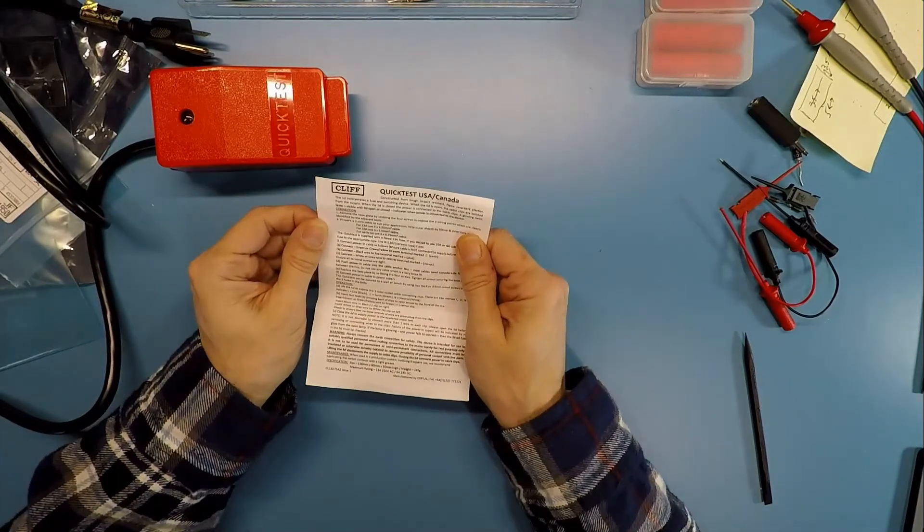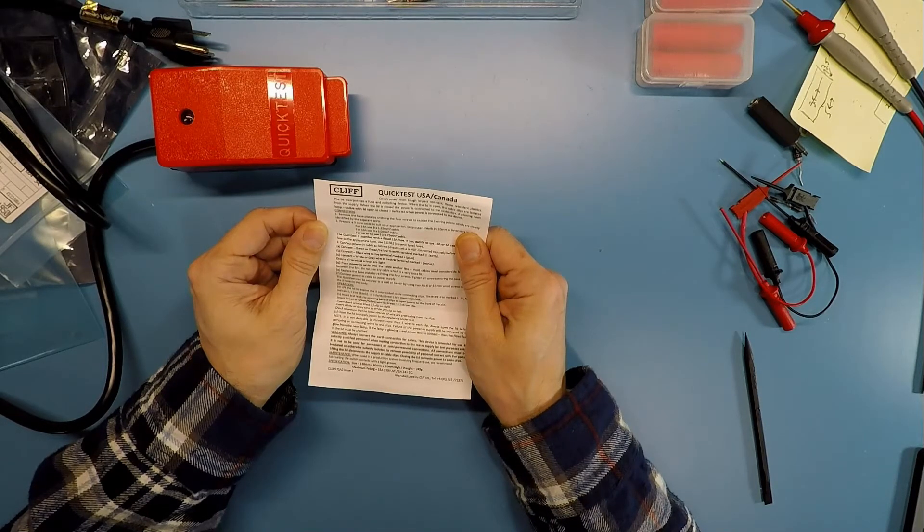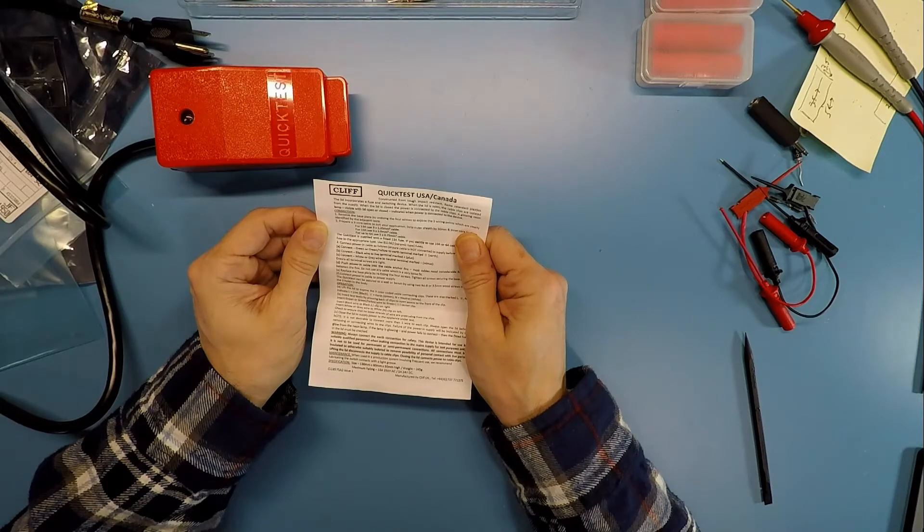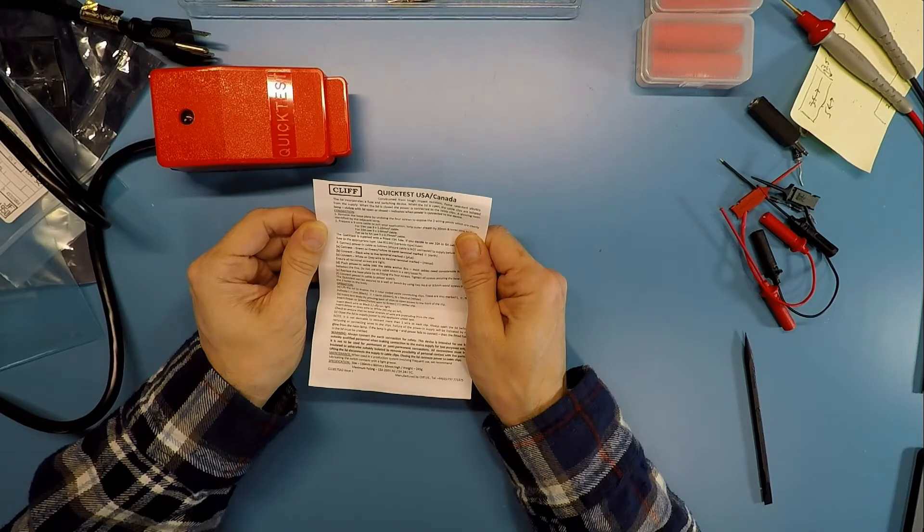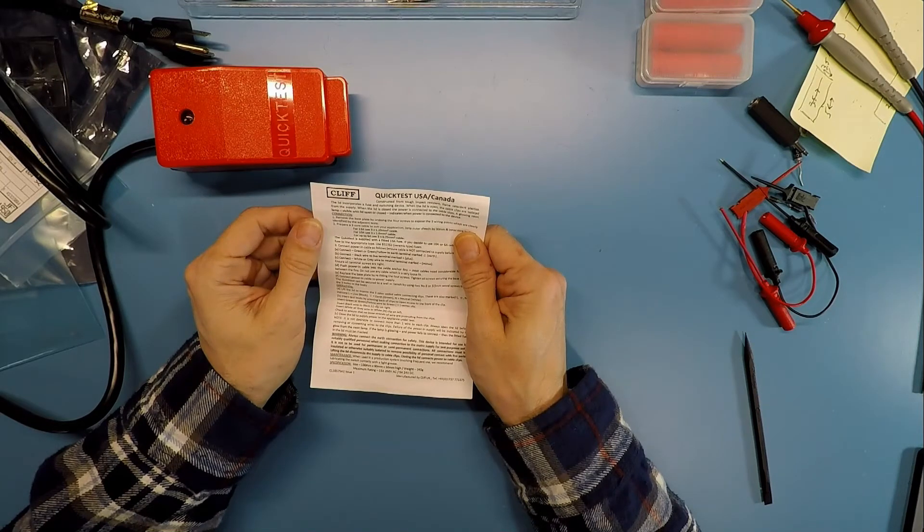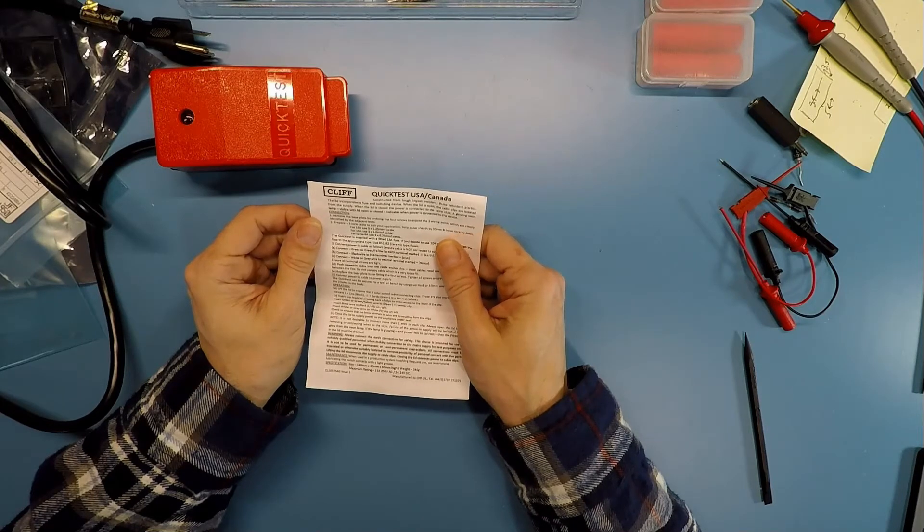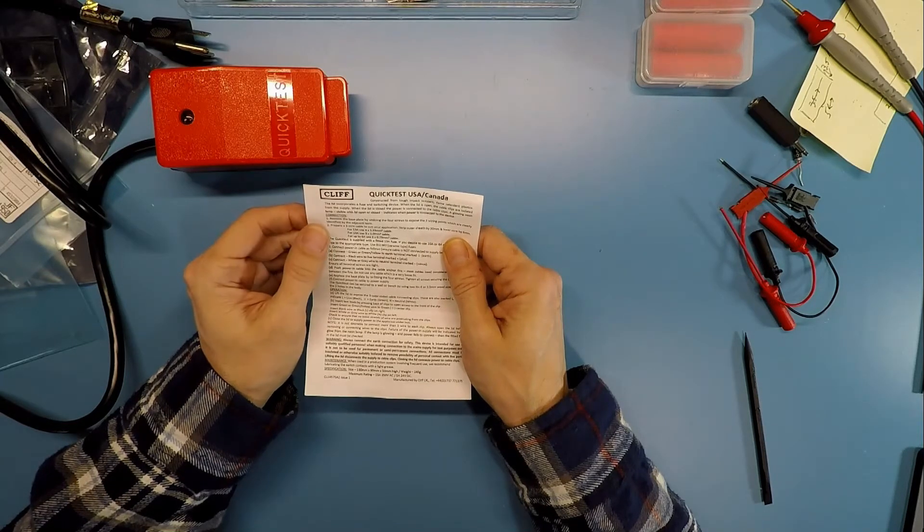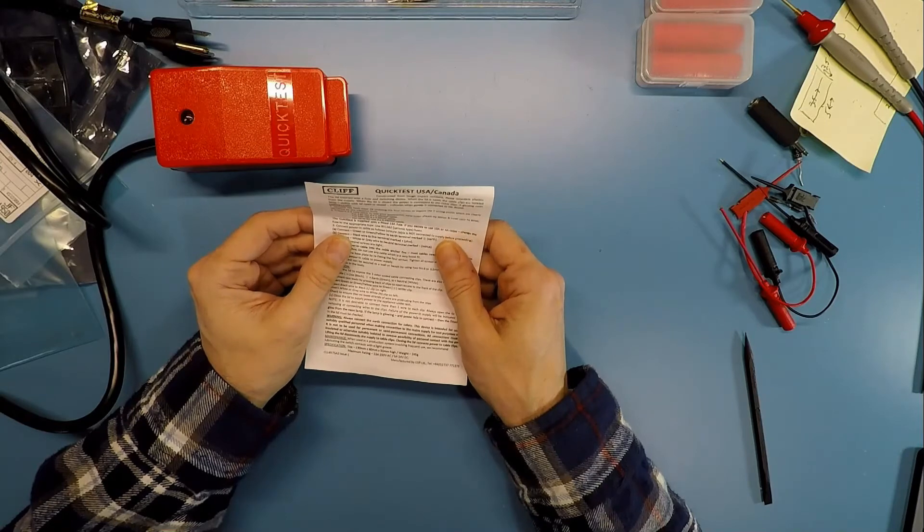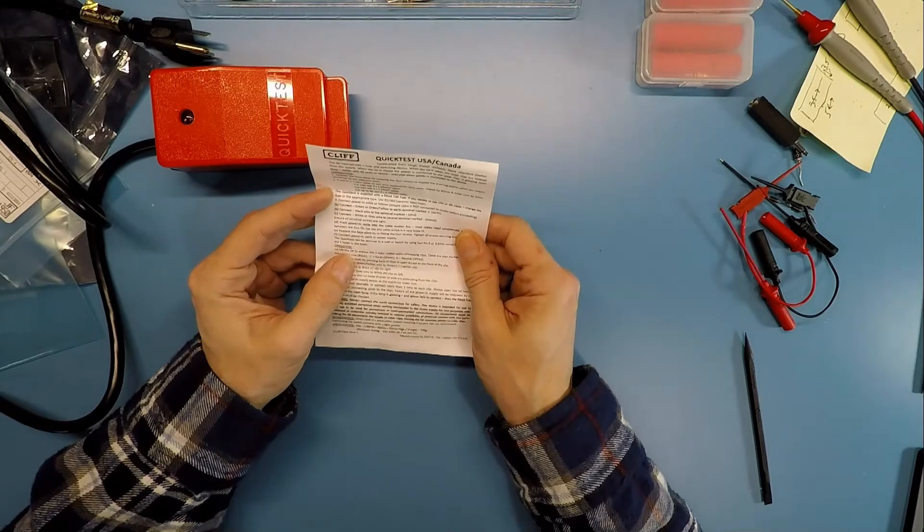Reading the instructions: the lid incorporates a fuse switch device. When the lid is open, the cable clips are isolated from the supply. When closed, power is connected to the cable clips. The glowing neon lamp, visible with lid open or closed, indicates power is connected. It explains to prepare a 3-core cable by stripping outer sheath about 30 millimeters and inner core about 6 millimeters, and recommends different fuses for different cable gauges and amperages.